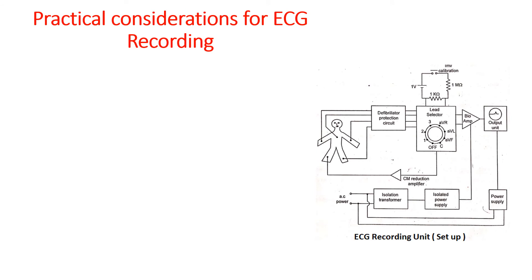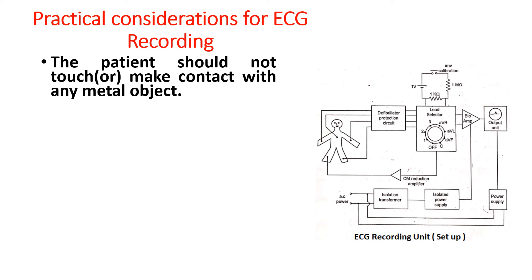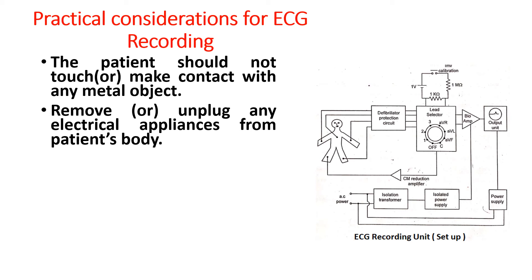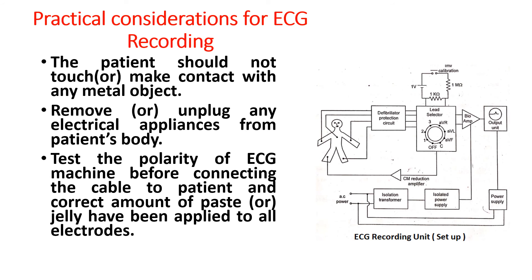Now we will discuss about the practical considerations for ECG recording. Before recording ECG, the operator should check that the patient does not touch or make contact with any metal object. Remove or unplug any electrical appliances from the patient's body. Test the polarity of the ECG machine before connecting the cable to the patient, and ensure the correct amount of paste or jelly has been applied to all electrodes.